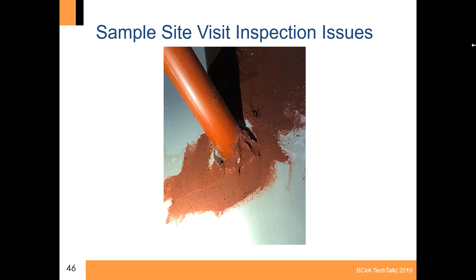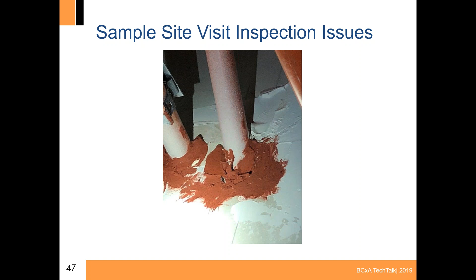You can see the hole into the space in this fire caulk. We asked the question if there was ever a hole in the fire caulk - this maybe isn't a good example, but even if you had one that looked like a nice installation with just one little hole, they said it might be okay, but it's an indication that something probably wasn't installed appropriately. And if it was a firewall, is that an issue? Probably not, because it expands. If it's a smoke barrier, then that is an issue.